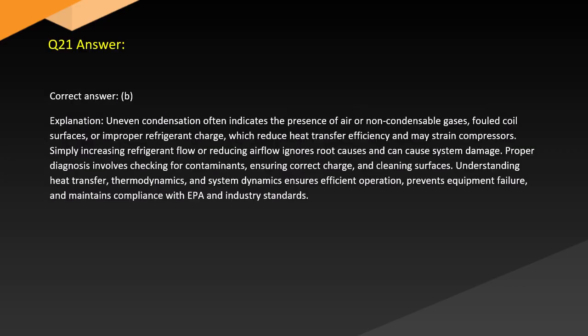Answer. Correct answer. B. Explanation. Uneven condensation often indicates the presence of air or non-condensable gases, foul coil surfaces, or improper refrigerant charge, which reduce heat transfer efficiency and may strain compressors. Simply increasing refrigerant flow or reducing airflow ignores root causes and can cause system damage. Proper diagnosis involves checking for contaminants, ensuring correct charge, and cleaning surfaces. Understanding heat transfer, thermodynamics, and system dynamics ensures efficient operation, prevents equipment failure, and maintains compliance with EPA and industry standards.